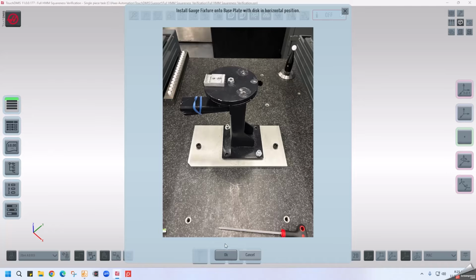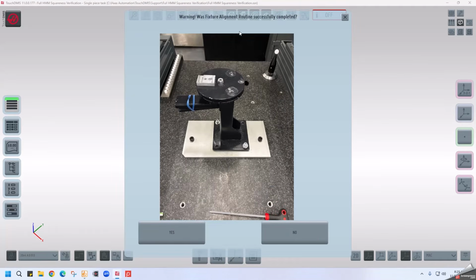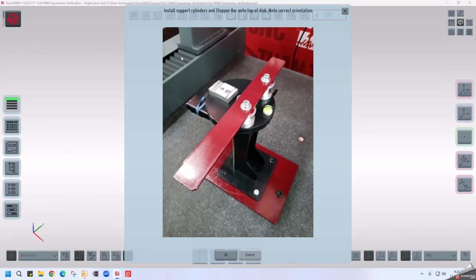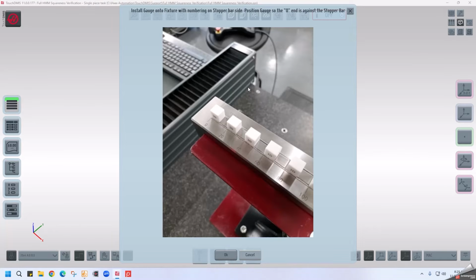Next, I need to install the fixture. Now, if you've moved the fixture from doing the full linear verification program, you need to select No. But since I am continuing straight from the full linear verification program, my fixture has not moved, so I can click OK. My stopper bar is already installed, so I'll select OK. Now I want to make sure that the 0mm marking on the step gauge is pressed up against the stopper bar. Then I'll select OK. But again, if you have already completed the full linear verification program, these steps should already be done.